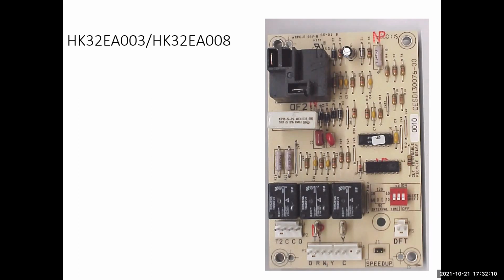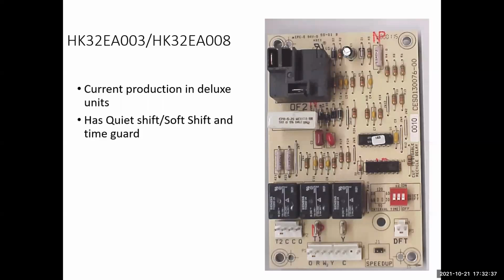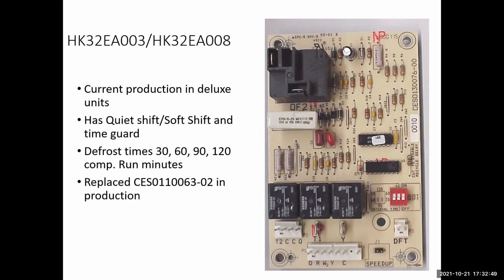The wiring for each of the controls is different than the 003 and 008. They incorporate a T2 connection used for the 5-minute anti-short cycling feature. And the 001 does not have a T2 terminal or the anti-recycle feature. That was production in the deluxe units. Quiet shift and time guard was added. This one has a defrost time of 30, 60, 90, and 120, and it replaces the old CES0110063-02.